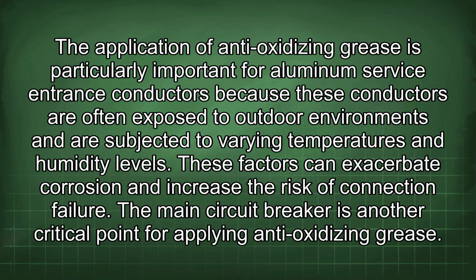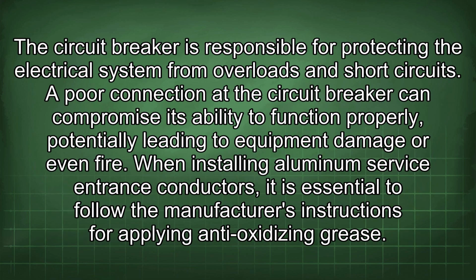The application of anti-oxidizing grease is particularly important for aluminum service entrance conductors because these conductors are often exposed to outdoor environments and are subjected to varying temperatures and humidity levels. These factors can exacerbate corrosion and increase the risk of connection failure. The main circuit breaker is another critical point for applying anti-oxidizing grease. The circuit breaker is responsible for protecting the electrical system from overloads and short circuits. A poor connection at the circuit breaker can compromise its ability to function properly, potentially leading to equipment damage or even fire.